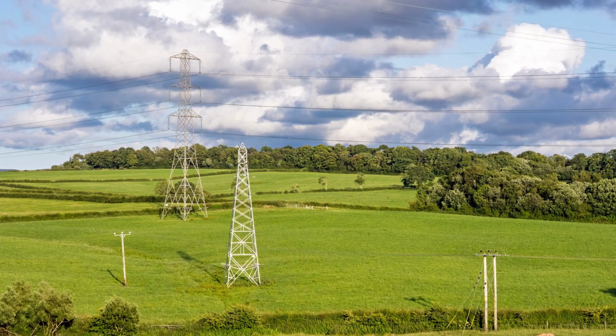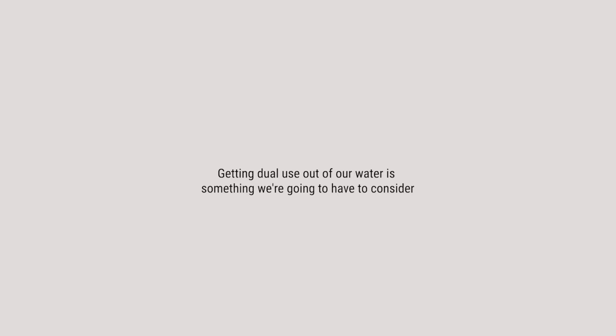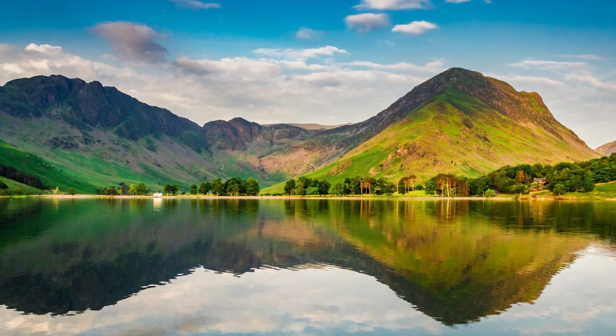Like I said earlier, alternative water sources here in the UK - we've got quite a few, and you don't necessarily have to go with one single solution. We are massively out of power at the moment, waiting decades for a connection to the grid, so we're going to have to make the most out of what we've got. Using the water by putting it through a plate heat exchanger first, raising the water temperature before putting it onto an evaporative system, getting dual use out of your water, is going to be something we'll have to consider - how much use can we get out of every single liter of water. And if we can't discharge that to atmosphere, do we just put it through the plate heat exchanger and back to wherever that water source is - if it's underground, if it's in a river - making the most of everything we currently have at our disposal.